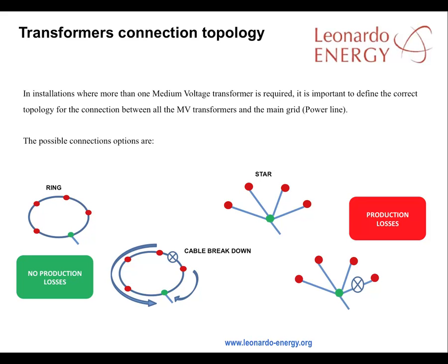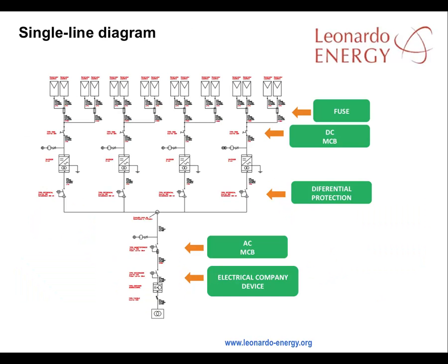In installations where more than one medium voltage transformer is required, it's important to define the correct topology for the connections across all medium voltage transformers and the power line on the main grid. This slide shows some of the characteristics of a ring versus a star topology. And here's a typical layout showing the electrical protections at a PV facility.